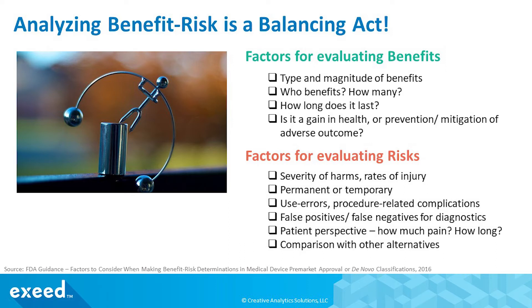When looking at risks, consider the severity of harm and type of injury. Is it permanent or a temporary effect? Does use of the device involve complicated steps which may result in use errors or procedure-related complications? If it's a diagnostic device, consider the risks of false positives and false negatives. At times, the benefit-risk analysis may need to be done at an individual patient level — how long has the patient been suffering and what is the intensity of pain? Risk tolerance may be different for different patients based on their circumstances, and high-risk devices may be approved for limited use by a narrow patient group in some situations.